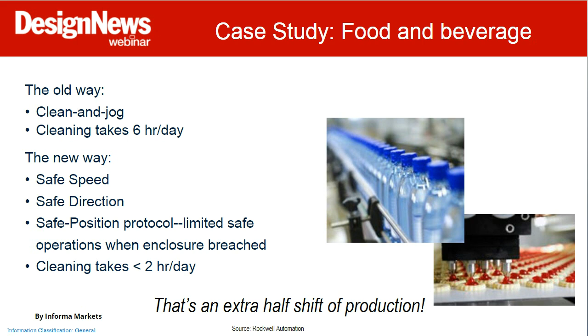Or actually, it could also have been done with a dumb drive and a safety PLC, but the capability is the key thing here. Now here's another example: this was manufacturing fuel injectors, and they were using functional safety to keep the equipment moving at safe limited speed around the operator, which helped. But the key thing they found is, when it's moving toward the operator, yeah, you definitely want safe limited speed, but when it's pulling away, it's not going to hurt them.